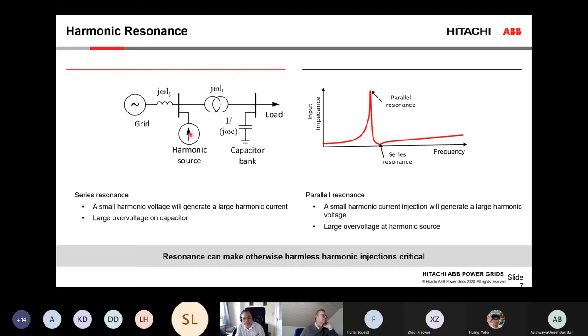The analogous problem could be that if this has some control system that makes it behave as a voltage source in the harmonic domain, so we have a fixed harmonic voltage here, and we happen to inject harmonics exactly on this series resonance frequency, the valley, even a small voltage will give us a huge current, and that could also cause damage to equipment and be a big problem.